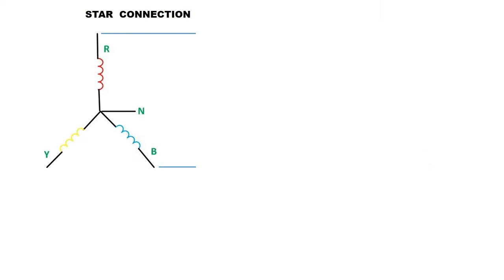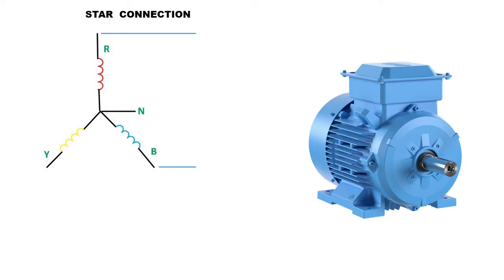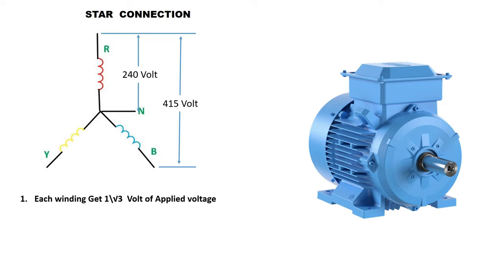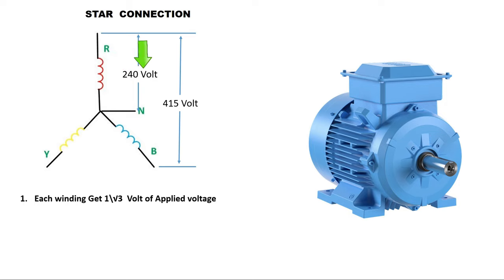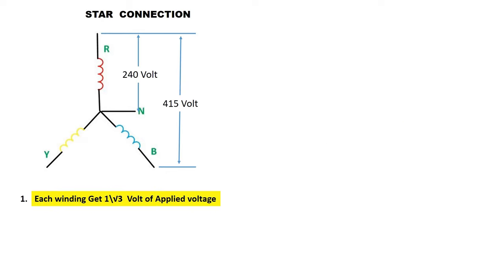If you connected your motor in star, then keep one thing in mind — to the winding of motor, you are giving only 240 volt power supply. The three phase power supply you connected has voltage 415 volt, but to one winding, voltage provided is only 240 volt. It means the motor winding is getting 1/root 3 of line-to-line voltage. Like in this picture you can see, between R phase and B phase voltage is 415 volt, but the R phase winding is getting only 240 volt power supply. Reason behind this is, we connected motor winding in star — on connecting in star, the center point will work as neutral. So if I measure voltage on both ends of R phase winding, I will only get 230 to 240 volt.